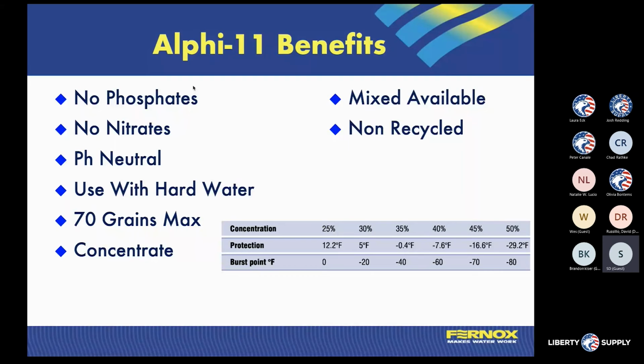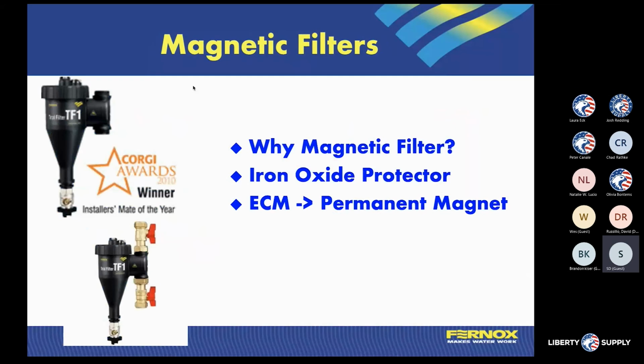With glycol, you have to remember it is an insulator. The more glycol, or the higher the percentage of glycol, I have in a system, the more energy I need to put into that fluid to get the temperature to rise. So you always want to make sure you have the proper amount of glycol for your system. You want to understand the difference between protection level and burst point. Protection is the point where we're still flowing water, and the burst point is the point, based upon those concentrations or mixes of water to glycol, where the system will freeze up. You just want to make sure you understand what you need for your different applications and systems. If not, you can always call Liberty Supply and we can help you with that process.